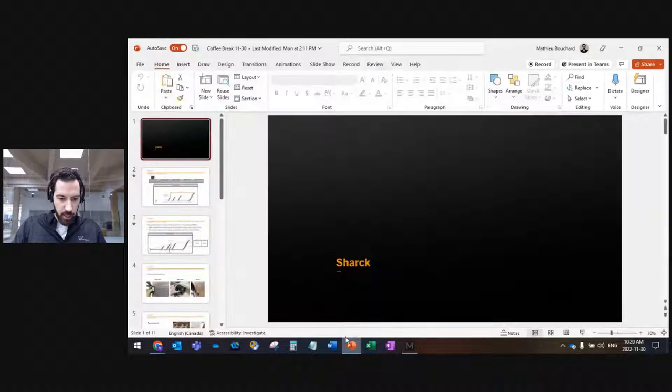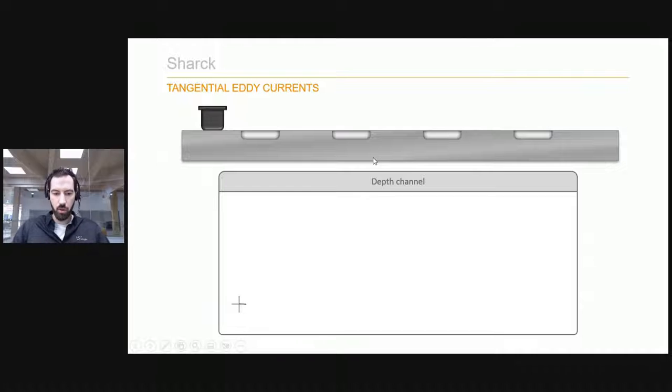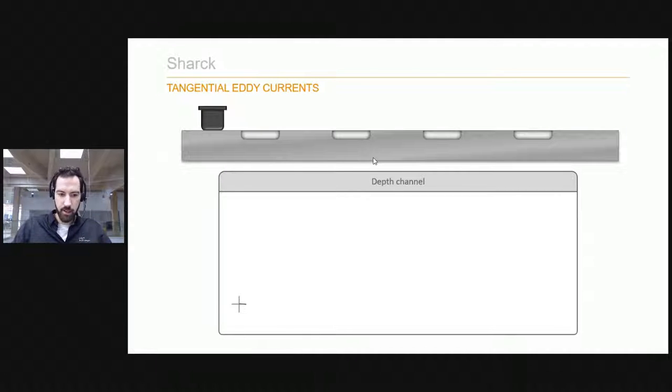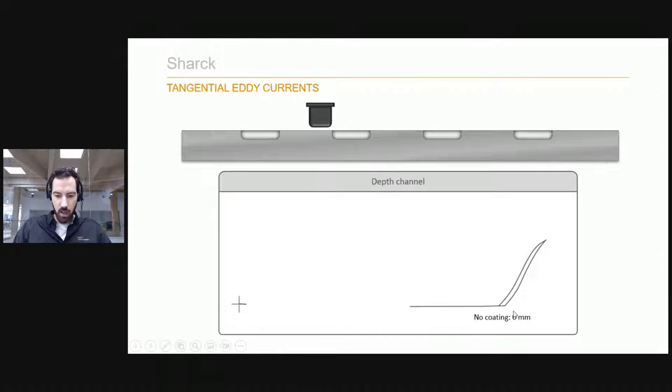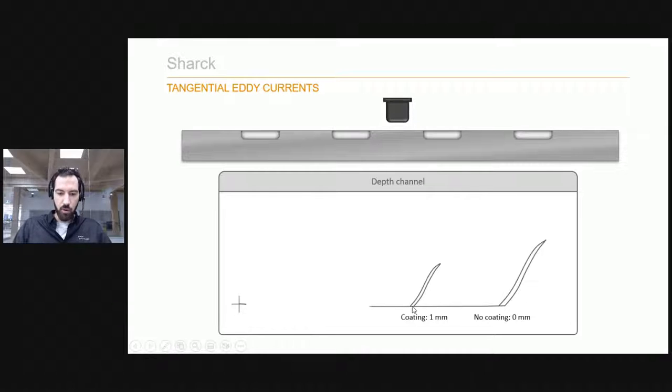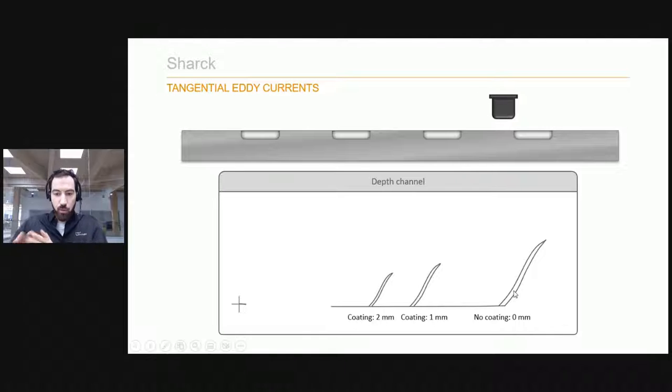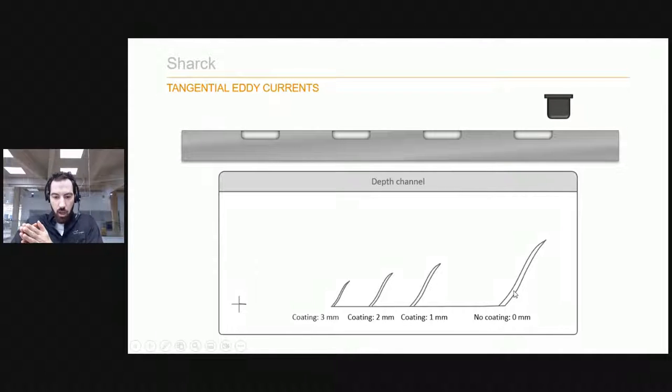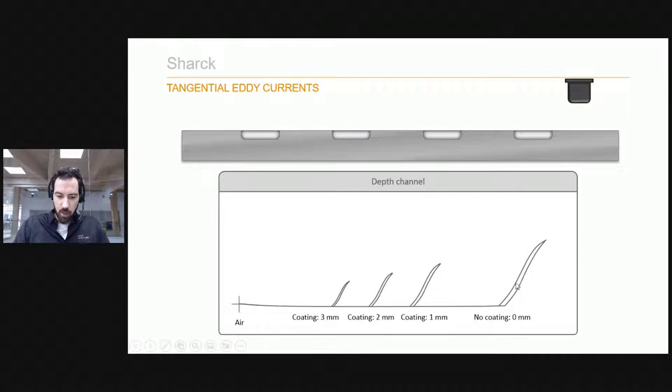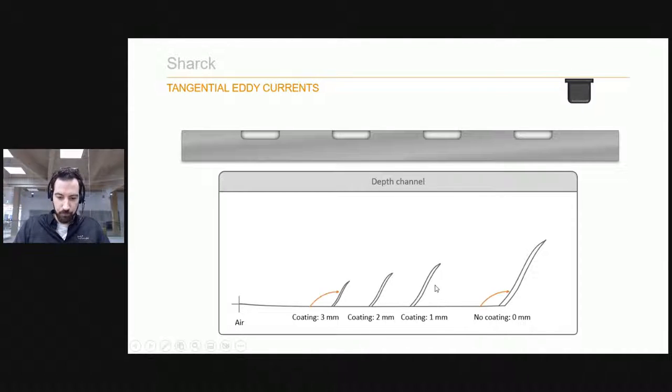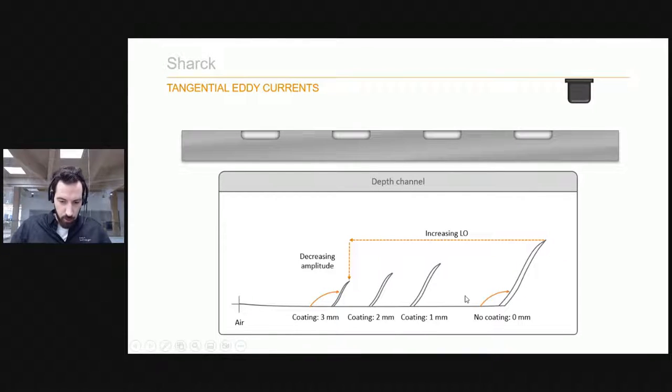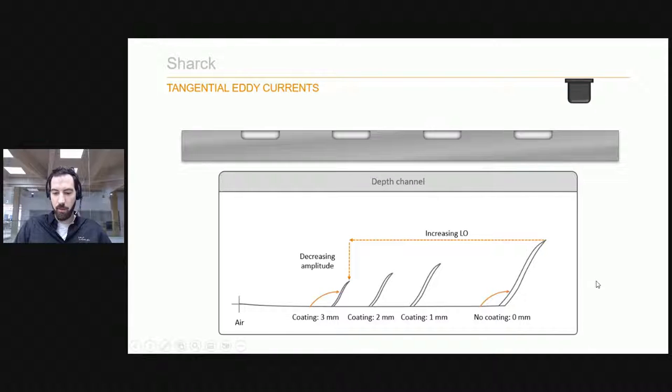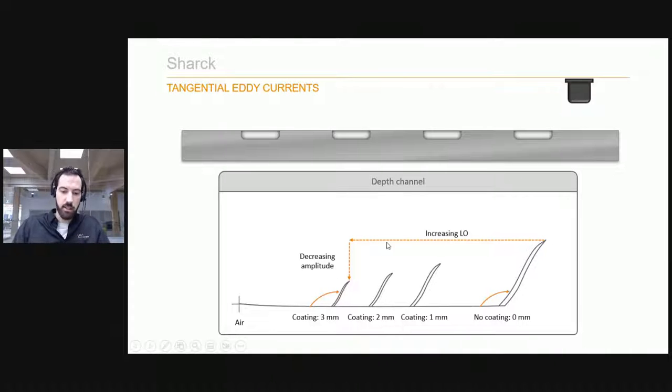I just want to take an extra few minutes to talk about applications. Just here is the concept of Shark that I've been trying to explain. As you can see, when you inspect a flaw, you'll get a certain signal. If you're adding more coating or more liftoff, it will be the same shape of signal, but moved onto the liftoff curve. The more liftoff you have, the more your flaw will show up on the left side of the impedance. This part is more for those familiar with eddy currents.